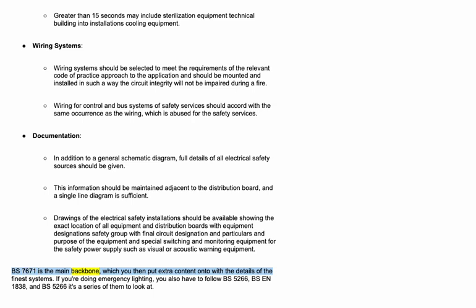BS 7671 is the main backbone, which you then put extra content onto with the details of the specific systems. If you're doing emergency lighting, you also have to follow BS 5266 and BS EN 1838. It's a series of them to look at.